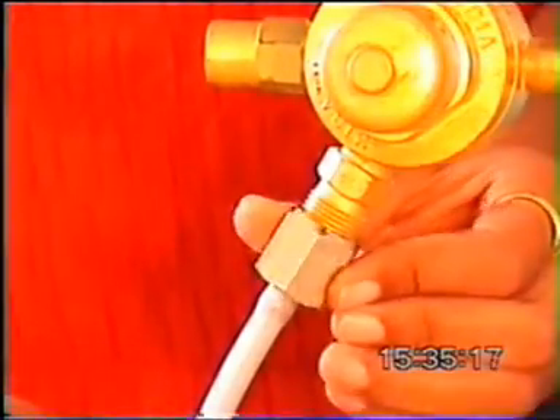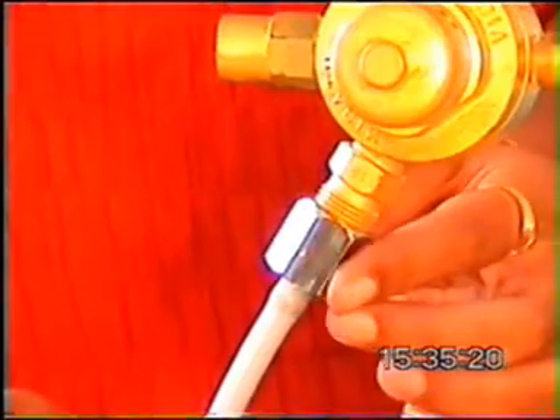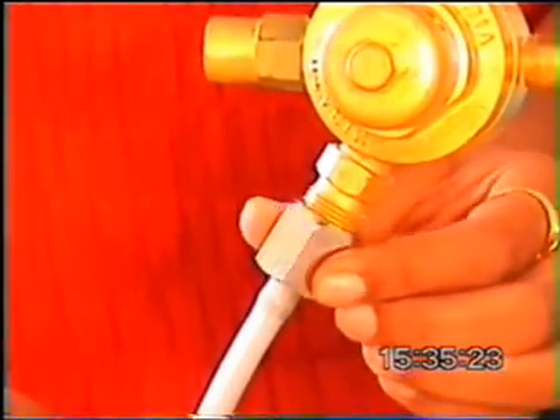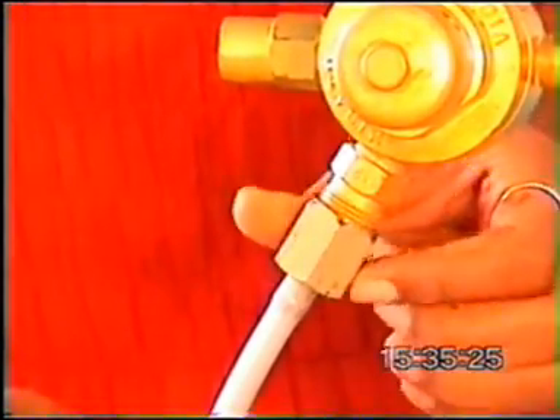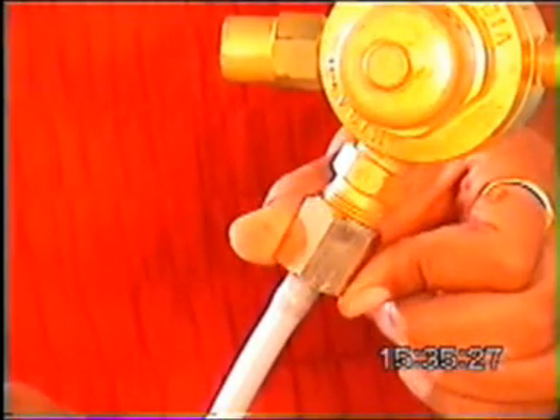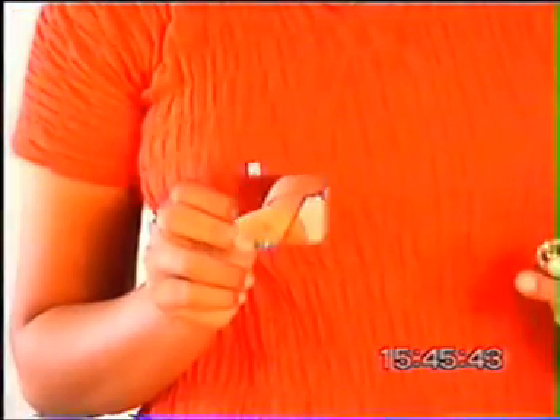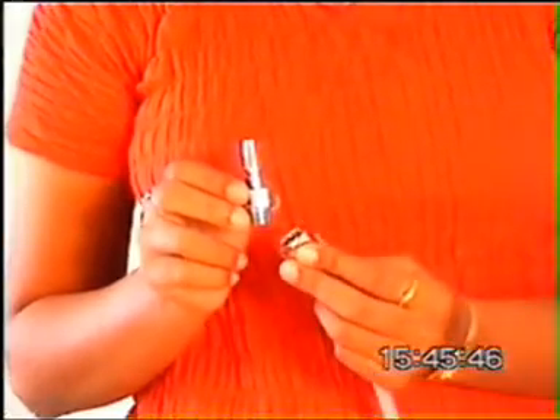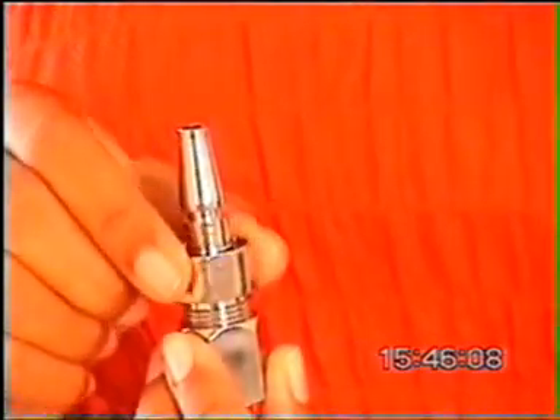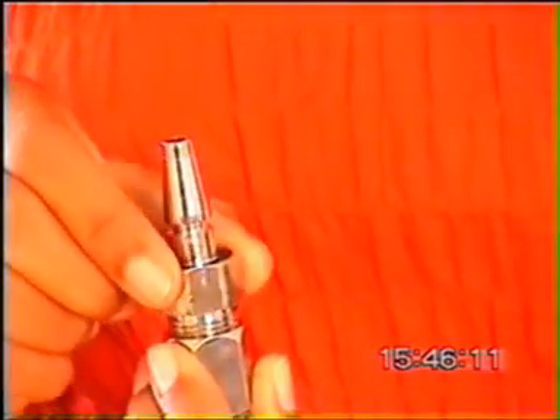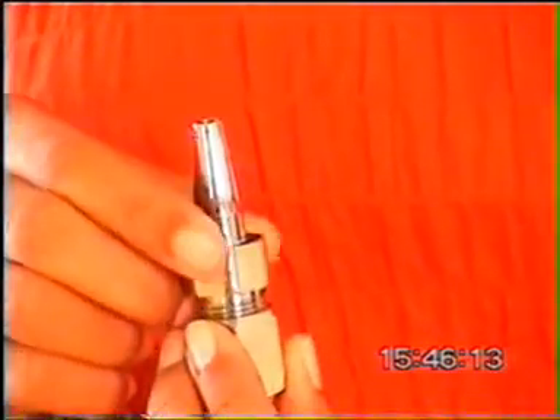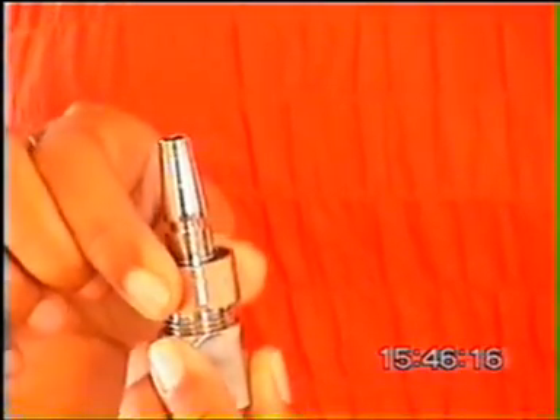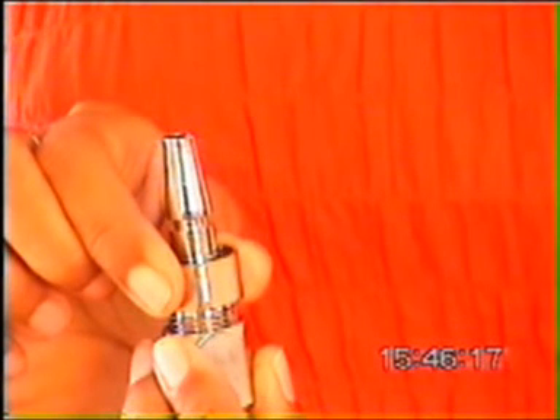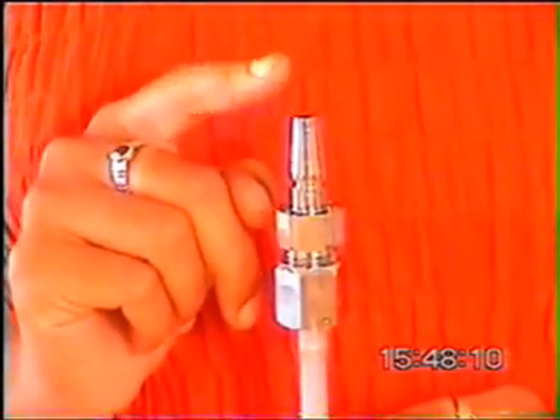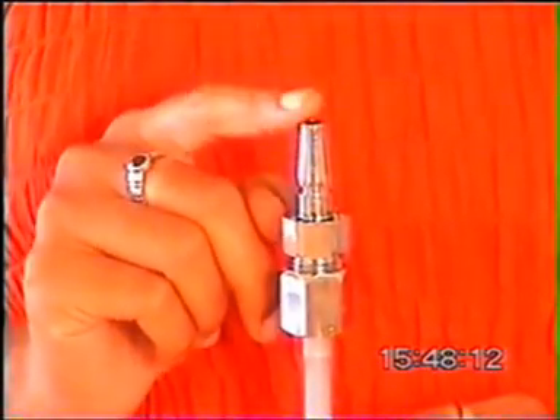A socket is screwed over the pressure regulator outlet and tightened securely. In place of the oxygen cylinder, the system can also be connected to the central oxygen supply available in most of the hospitals. A special connector plug is used to connect the system to the central oxygen supply. The plug is screwed over the connector which is used for the oxygen regulator. The special connector can now be attached to the wall socket of central gas line.